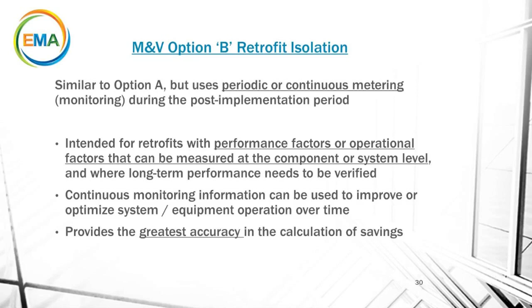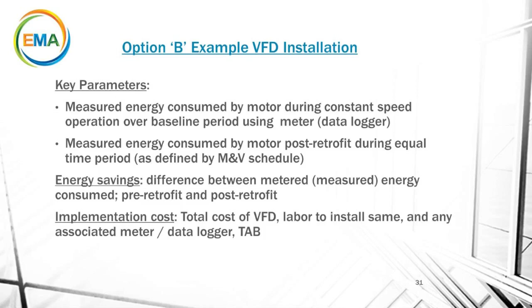Option B, typical example is a variable frequency drive, VFD, installation. Measured energy consumed by the motor during constant speed operation. Measured energy consumed by the motor post retrofit during an equal time period. Now the key thing is we're putting that variable frequency drive on there that we can adjust based on demand. Really understanding your load conditions and your system conditions is key. However, you could get some great energy savings. The savings is the difference between the metered energy consumed pre-retrofit and post-retrofit, and the implementation cost is the total cost of the VFD, the labor to install, and any associated meter data logging, testing, adjusting, and balancing. You want to save the energy without disrupting the entire system during these examples.